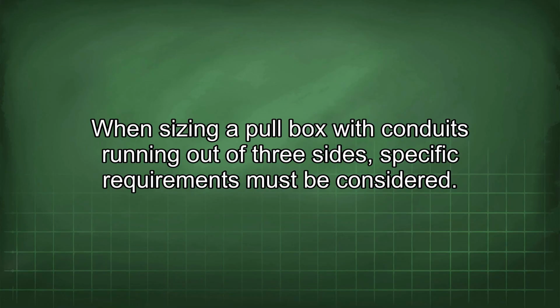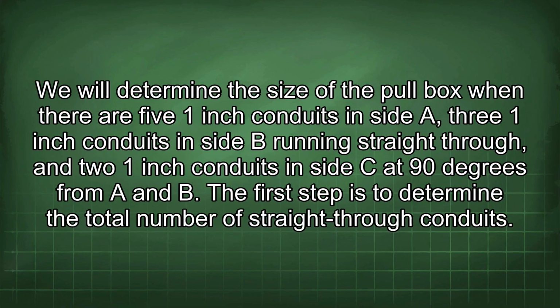When sizing a pull box with conduits running out of 3 sides, specific requirements must be considered. We will determine the size of the pull box when there are 5 1-inch conduits in side A, 3 1-inch conduits in side B running straight through, and 2 1-inch conduits in side C at 90 degrees from A and B.